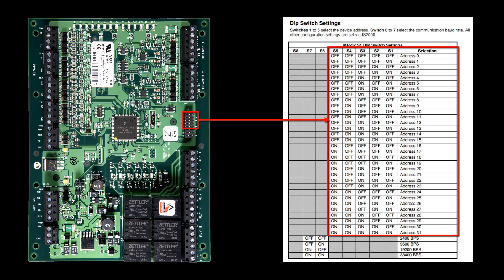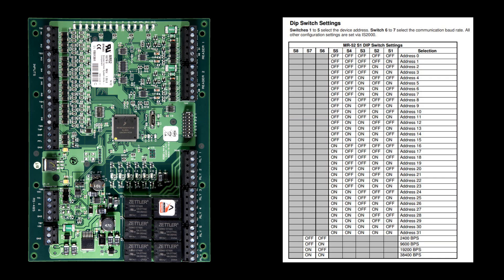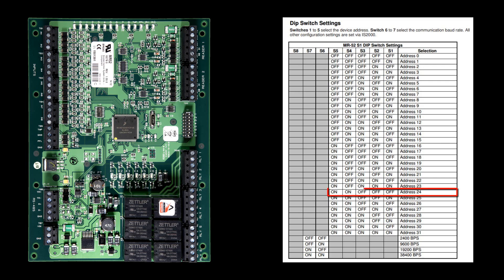DIP switches 1 through 5 are used for the addressing. S1 is 1 bit, S2 is 2 bits, S3 is 4 bits, S4 is 8 bits, and S5 is 16 bits. So if we wanted our MR52 board to be address 0, we would leave all DIP switches from 1 to 5 in the OFF position. If we wanted address 24, we would need to turn S4 and S5 on, because S4 is 8 bits and S5 is 16 bits, which totals 24.